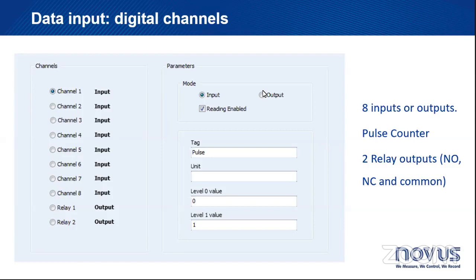But I can also enable them to operate as Modbus channels. Why is that useful? Well, imagine you have the FieldLogger connected to a SCADA system, okay? And the FieldLogger is actually not generating alarms. The SCADA system is the one that is dealing with the alarms, for example. And you wanted to have an output. Well, my SCADA system will write on the FieldLogger's register and tell it to turn on and off its output. So the FieldLogger in that case can operate as an alarming unit, or a SCADA system could send a command to it and it will command its output. Okay, so those are the two possibilities as outputs. This works for the eight digital channels or for the two relays.